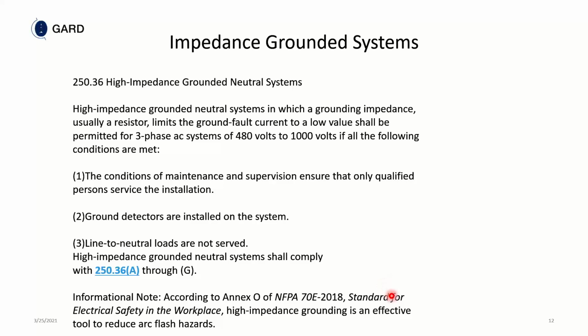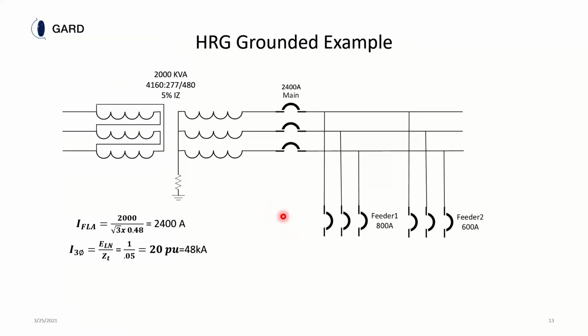Because 230.95 said that if you had a system that's 480 volts or greater, with more than 150 volts to ground, and greater than 1,000 amps, you must trip. But this clause says that if you're over 480 volts to 1,000 volts, you don't have to trip at all if you limit the fault current to a low value. So let's see how that looks now if we have a resistance grounding system.